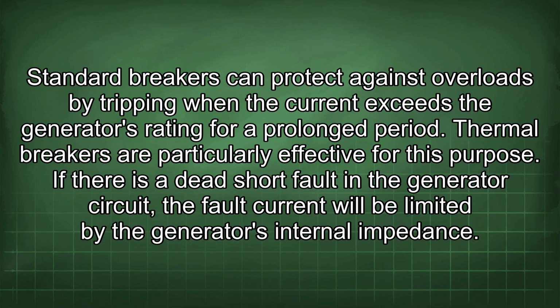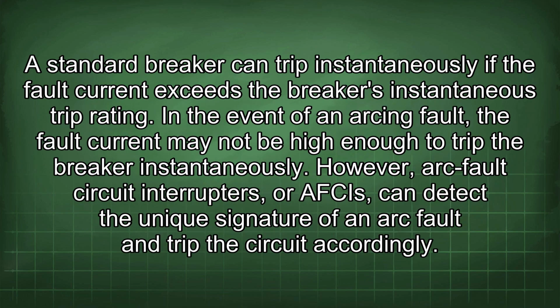If there is a dead short fault in the generator circuit, the fault current will be limited by the generator's internal impedance. A standard breaker can trip instantaneously if the fault current exceeds the breaker's instantaneous trip rating. In the event of an arcing fault, the fault current may not be high enough to trip the breaker instantaneously. However, arc fault circuit interrupters, or AFCIs, can detect the unique signature of an arc fault and trip the circuit accordingly.